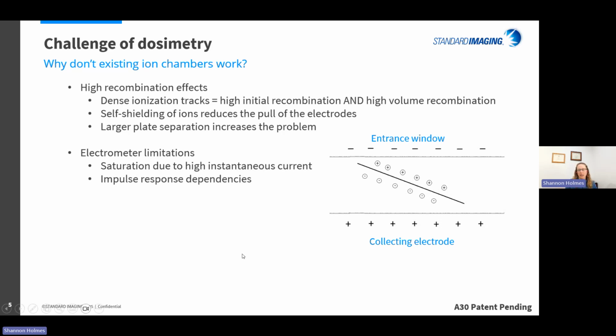There's also, in addition to this, some limitations with an electrometer for the readout of this device. So you can have saturation due to a really high instantaneous current, and then you have what are called impulse response dependencies. An impulse is an input signal that's really a delta function. It's a really sharp spike of signal, short rise time, short fall time, with nothing else around it, or if you have pulses, then those are separated. The electrometer, in my cartoon here, has some sort of rise time that it's dealing with, and then some sort of decay time. And so this impulse input becomes a more smoothed out curve with your electrometer, to a greater or lesser degree, depending upon your electrometer.